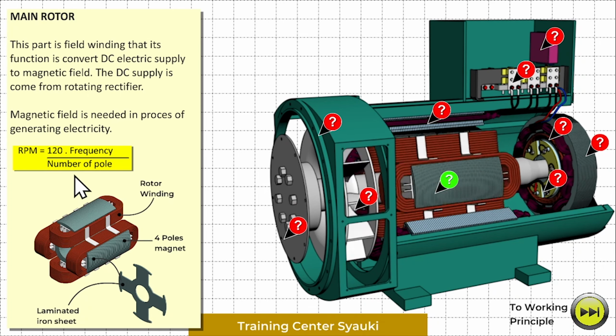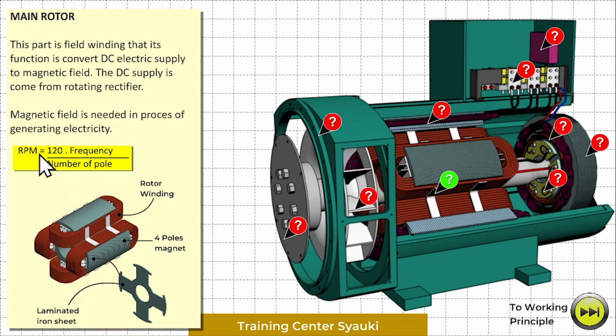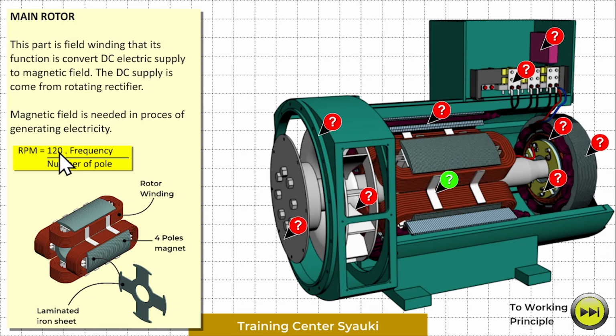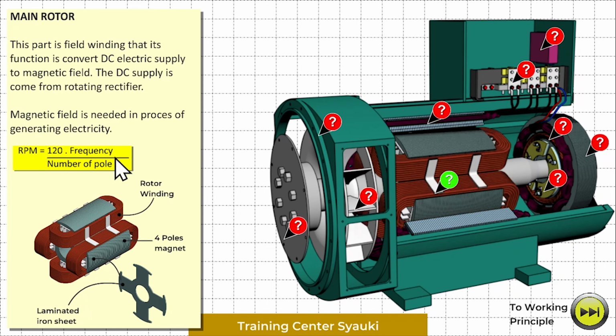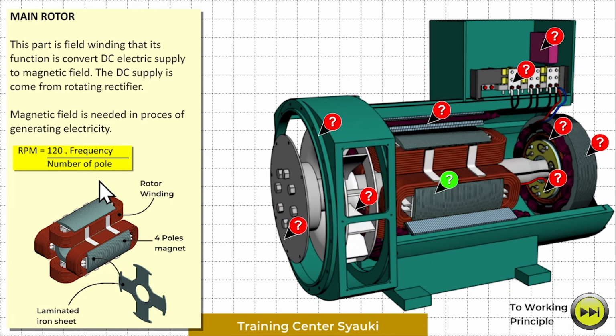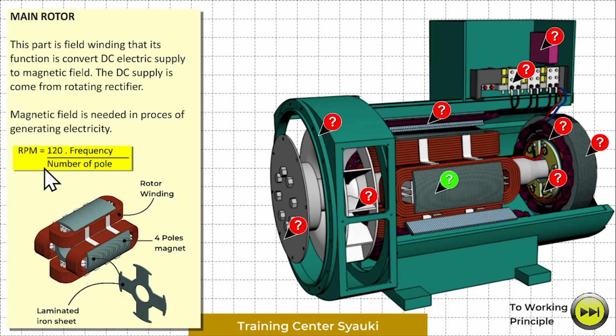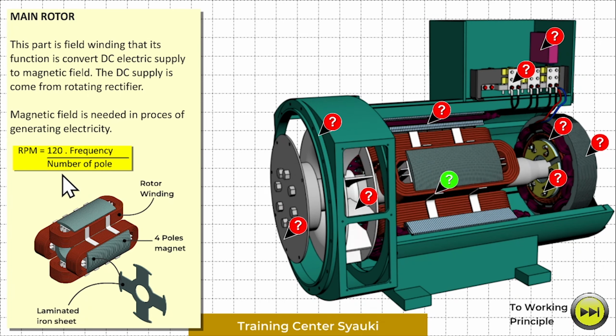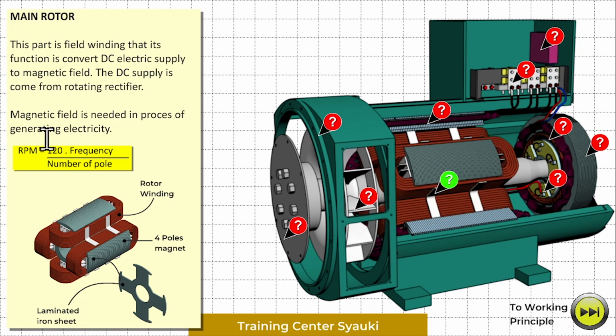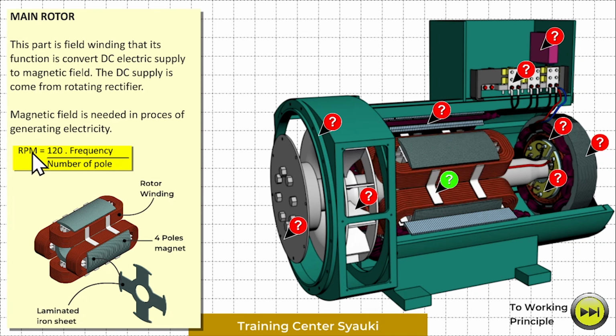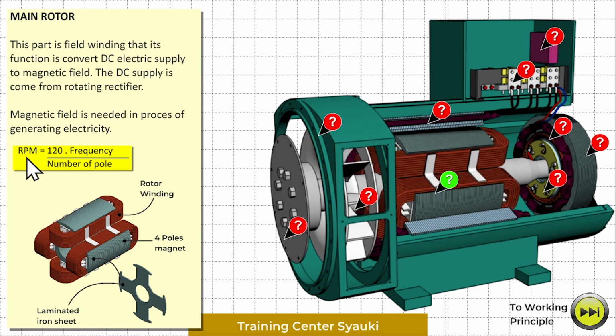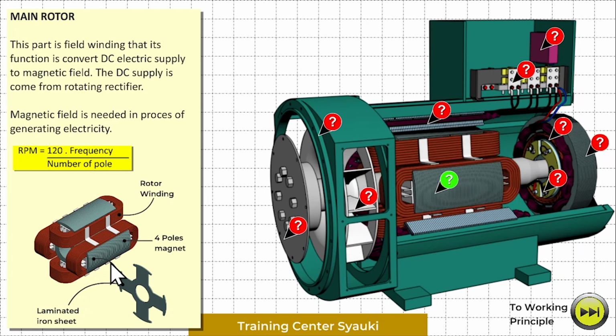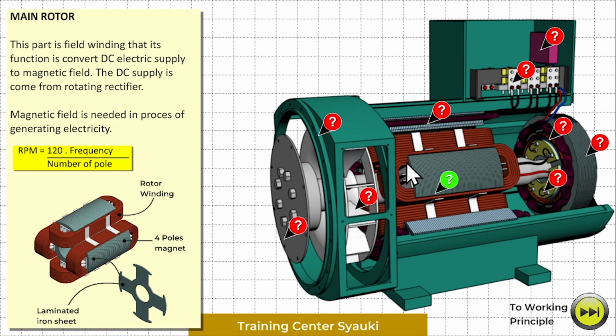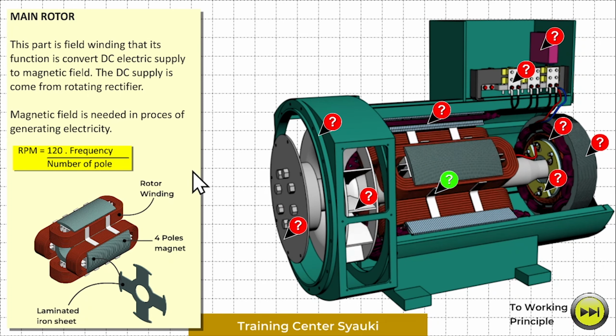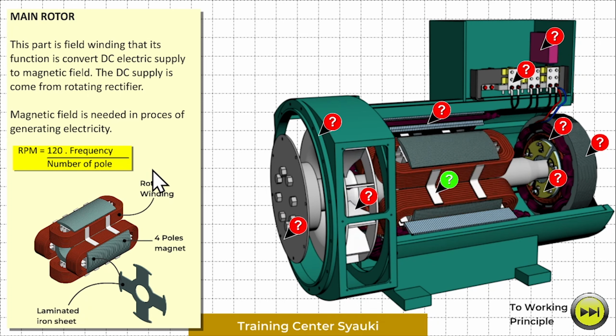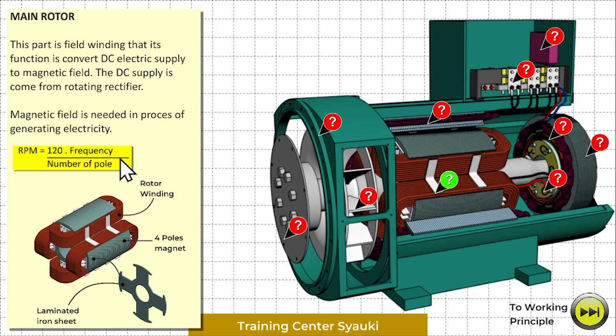As we can see here, there is formula RPM equal 120 times frequency divided by number of poles. So if we want the frequency to be 50 Hertz in my country, we need 1500 RPM if we have 4 poles magnet in rotor. If you have a different system and different requirement, please use this formula.